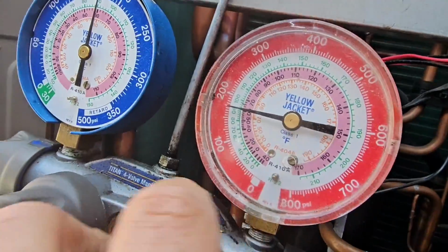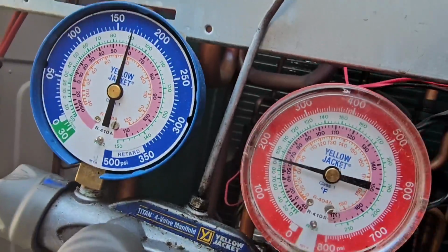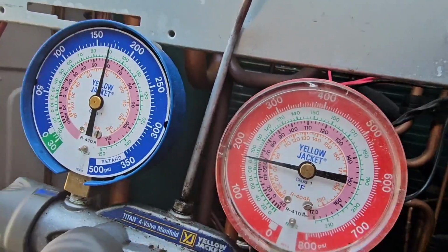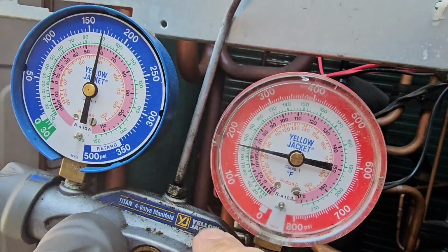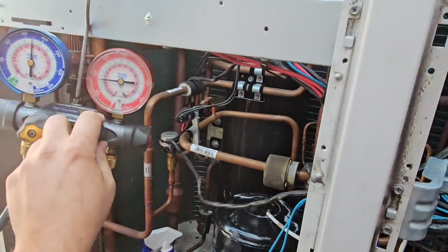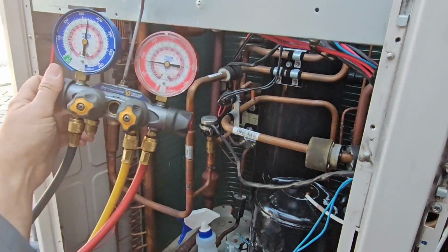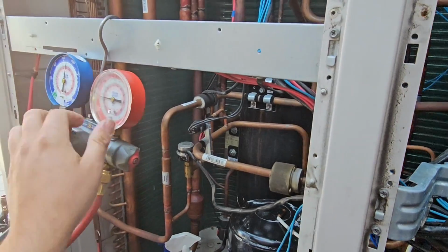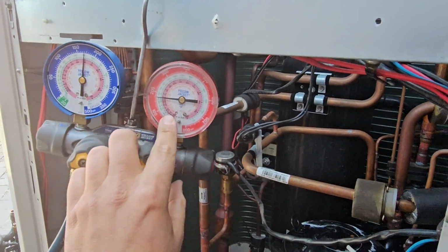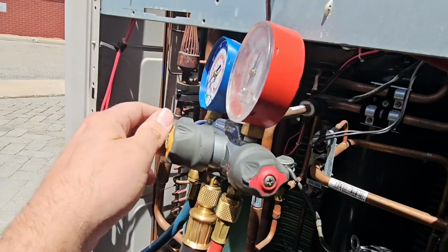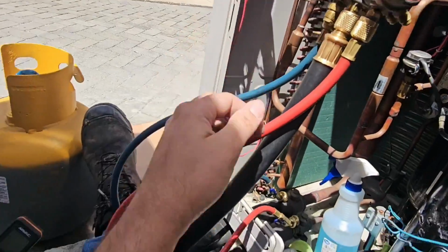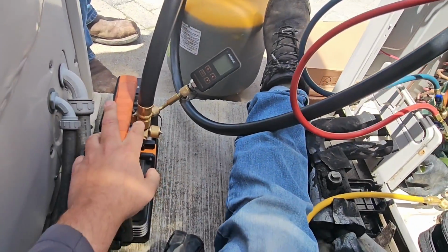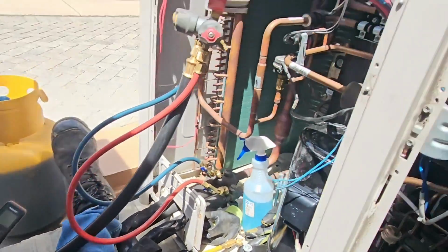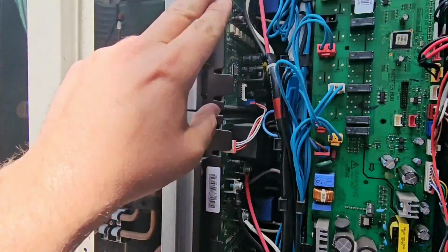We got about 175. I'm gonna let it set for probably at least 30 minutes, maybe even an hour, just to make sure we don't have any leaks. And then we'll put about probably at least 350 psi on this. Releasing all the nitrogen, getting the vacuum pump hooked up, and while I pull a vacuum, I'm going to replace both inverter boards.